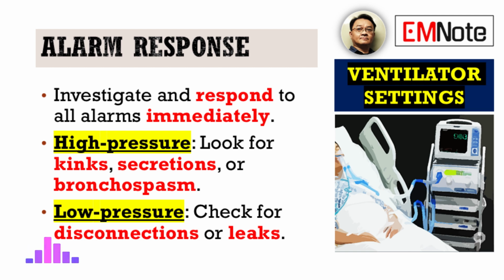Your immediate response to any alarm is always patient assessment first. Look at the patient. Okay, so what's the absolute first rule when a ventilator alarm activates? What do you do immediately? You must investigate and respond to all ventilator alarms immediately. Never, under any circumstances, ignore an alarm or just silence it without first assessing the patient and identifying the cause. The very first step is always to look at the patient, not just the machine flashing lights. Assess their breathing, their color, their level of distress. Is the chest rising?